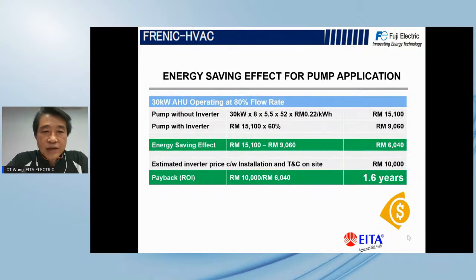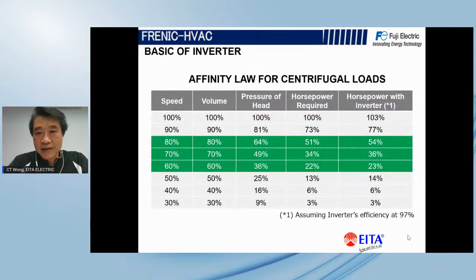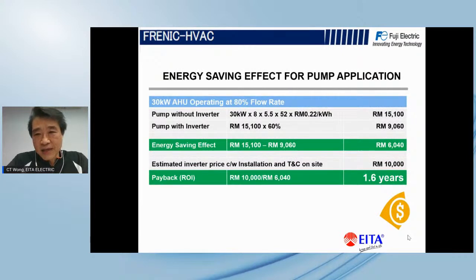Let us look into a quick calculation on the pump side. You can see the example of a 30 kilowatt pump or AHU that you can run at 80% flow rate. From here you can see that without an inverter, in 1 year you consume 15,100, even though I put a very low electricity rate. With inverters, as just now, the consumption is only 54%. Okay, I put it higher, you consume 60%. So from there, the ROI only needs 1.6 years. So bear in mind that with the latest technology, we can help you save more on energy.